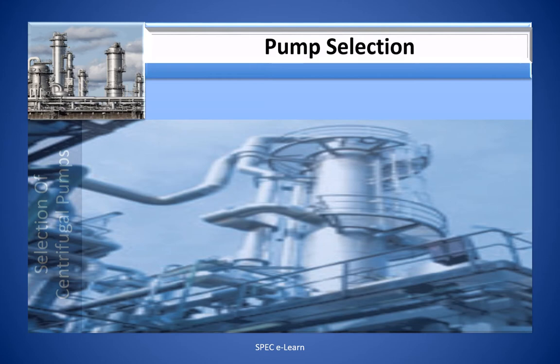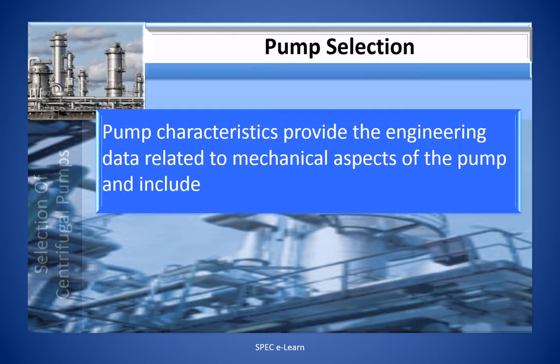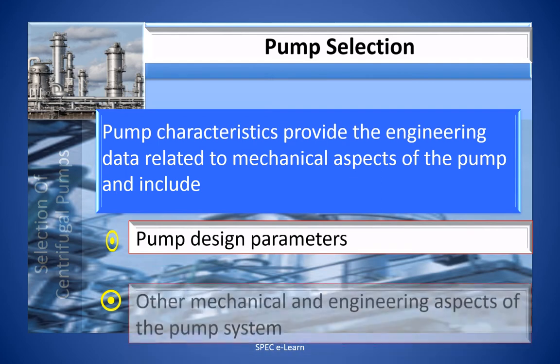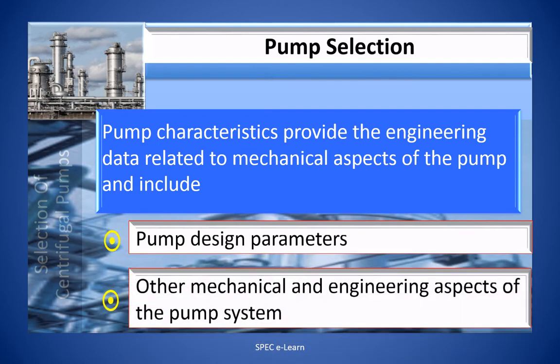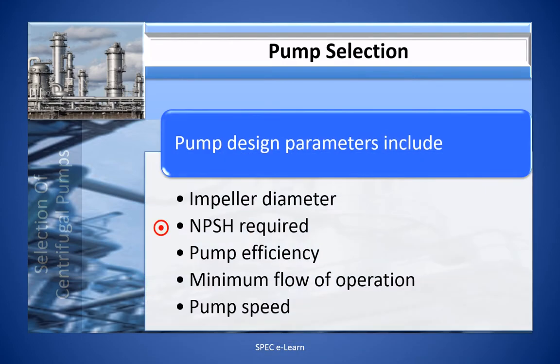Pump characteristics provide engineering data related to the mechanical aspects of the pump and include pump design parameters and other mechanical and engineering aspects of the pump system. Among the pump design parameters, those important from the process requirement and pump reliability viewpoint are impeller diameter, NPSH required, pump efficiency, minimum flow of operation, and pump speed.